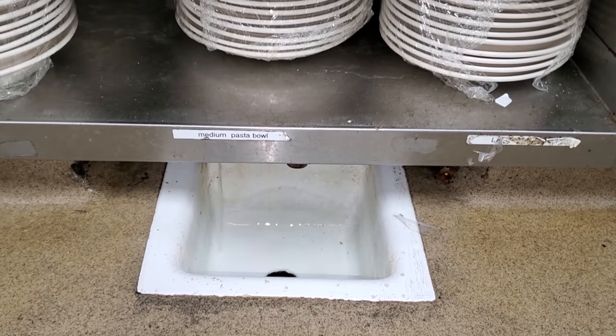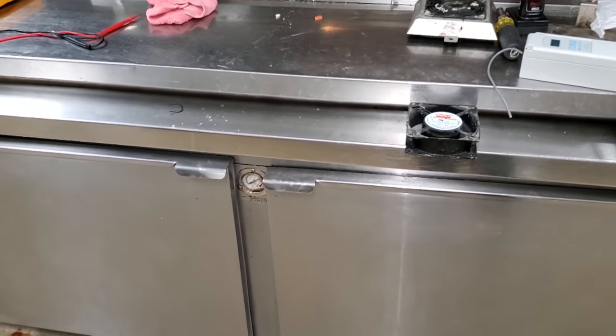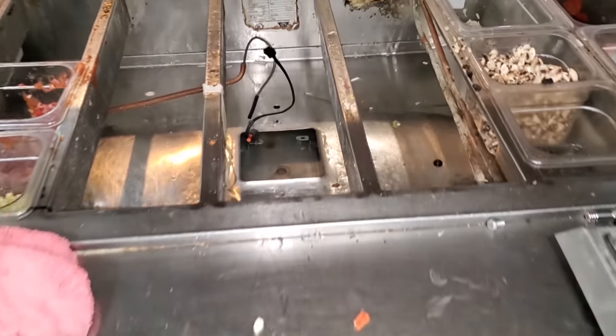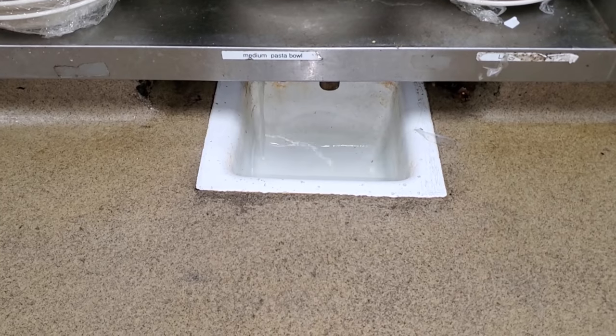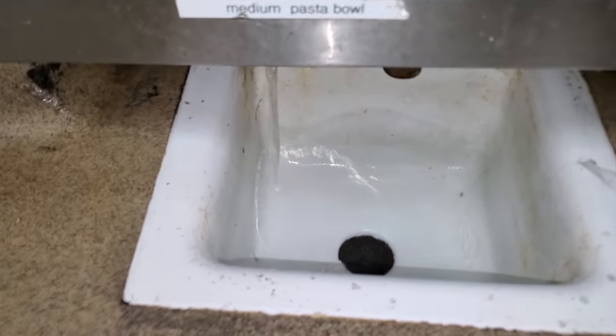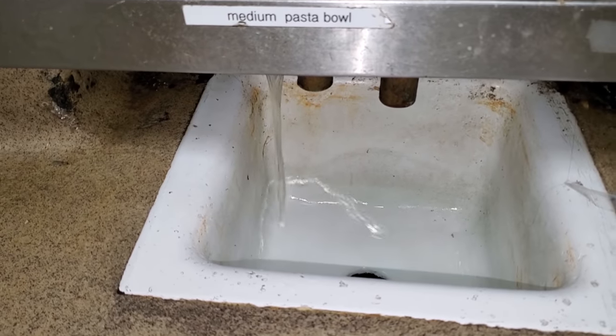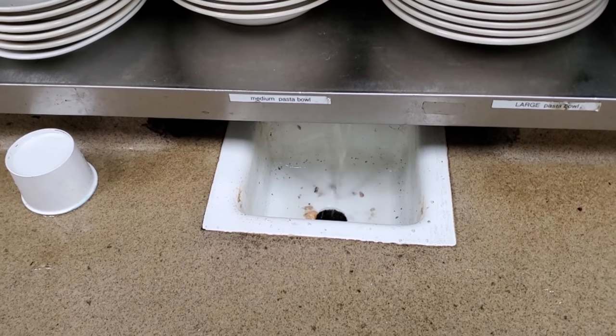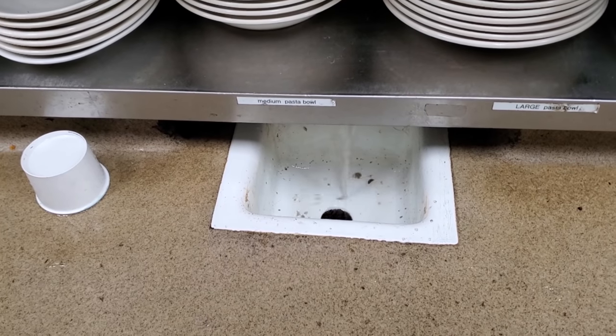This base section is connected, and on the other side there's another base section. So if the drain's plugged, it could overflow bleach water inside the box — you really got to think about that. You can see the chunks of stuff coming out of that drain. We've got a nice clean pan chiller.